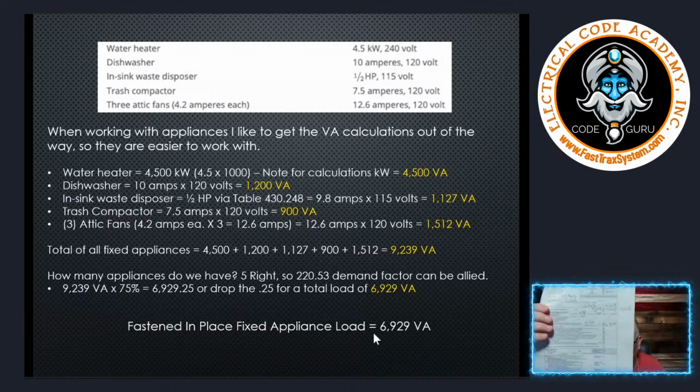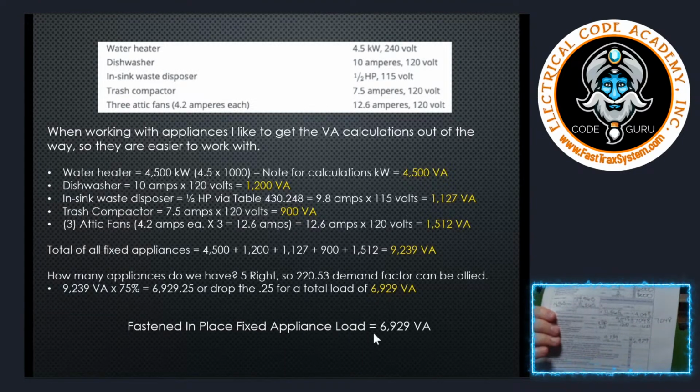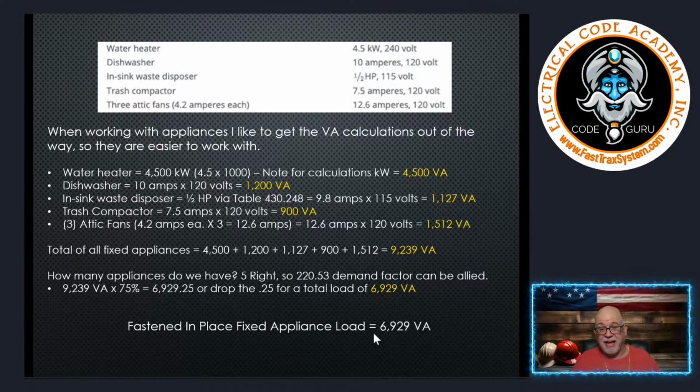Okay? Now, you might say, let's move on to the dryer. But remember, what we're doing while we're going down this list, we're working on that neutral at the same time. I love to work at the same time. So when you look at these loads here, notice something. There is only one of them here that utilizes no neutral. That is the water heater. Water heaters do not use a neutral. Okay, it's just a heating element. Doesn't have a neutral element to this.